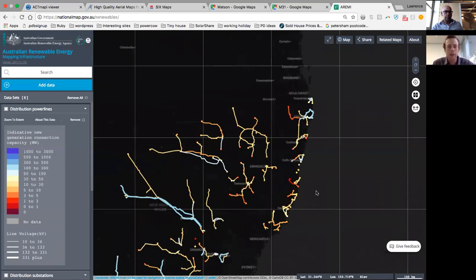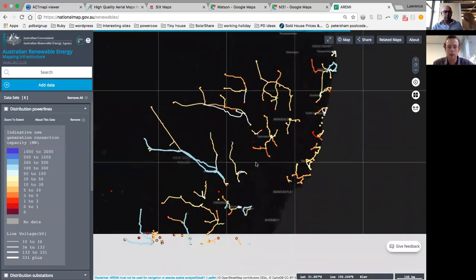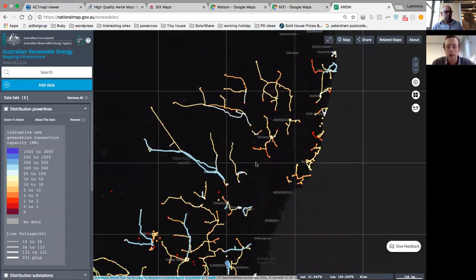But remember to pick a size of generation connection asset that's appropriate for your generator. Like we talked about before, those very high voltage power lines are fine if you're building 30 megawatts, but that'll be a horribly expensive connection if you're trying to build 1 or 200 kilowatts. So finding areas in the 1 to 3 or 3 to 5 range, or even 0 to 1, might be just right for a generator of that size.